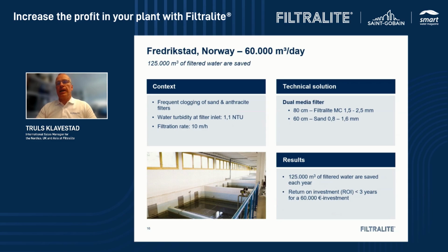In this case, they changed. They kept the sand in the bottom, but they took out the anthracite and replaced it with Filtralite. So they had a saving of 125,000 cubic meters each year, and return of investment was less than 3 years.